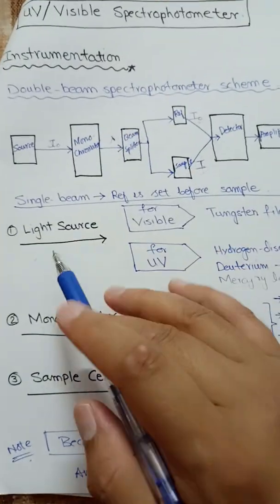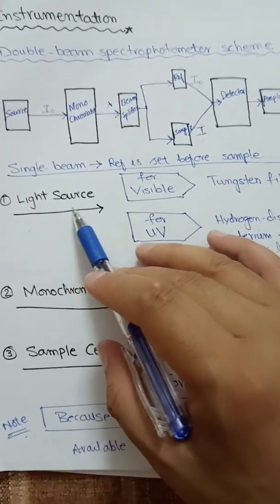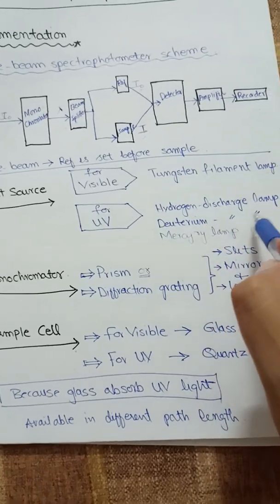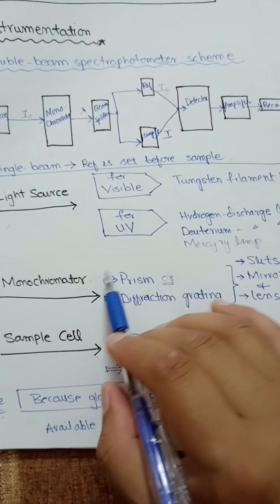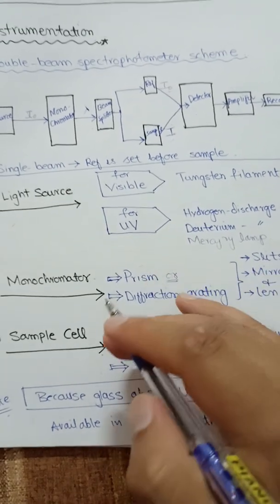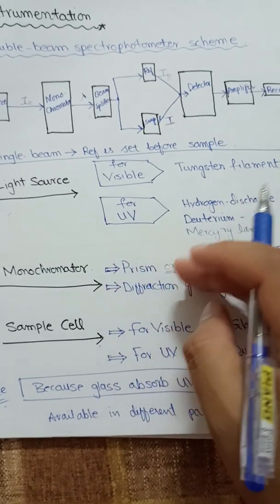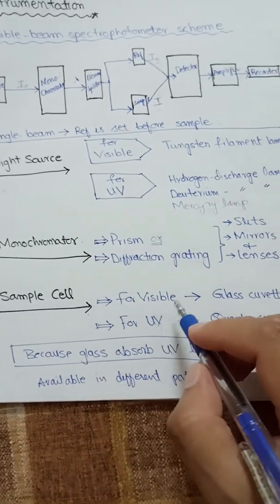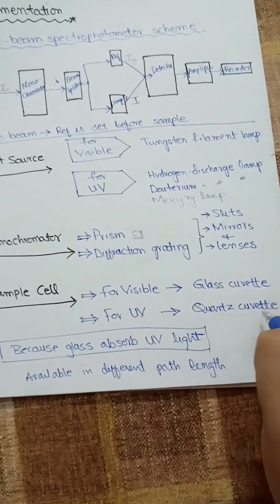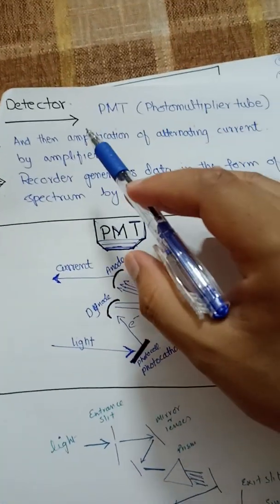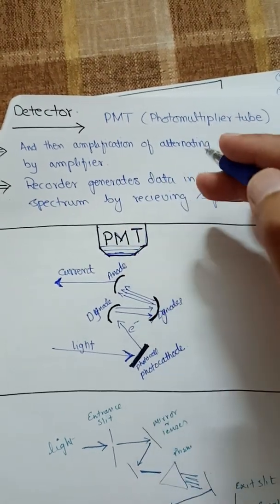Different instrument components include: light sources — tungsten filament for the visible region, and hydrogen discharge, deuterium, or mercury lamps for the UV region. The monochromator consists of a prism or diffraction grating with entrance and exit slits, mirrors, and lenses to isolate a single wavelength. For sample cells, glass cuvettes are used for visible light, and quartz cuvettes for UV, since glass absorbs UV radiation.